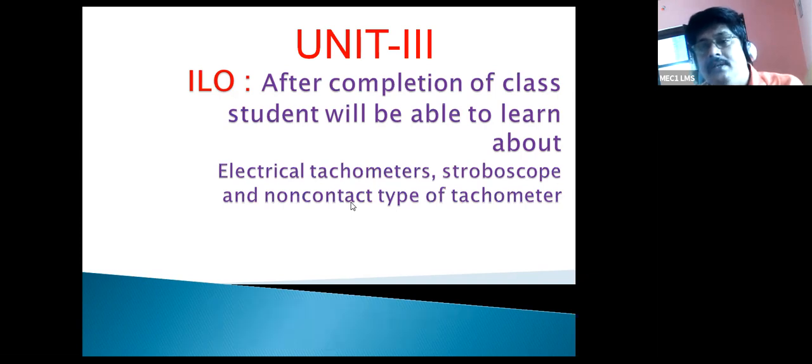The dust particles at the high intensity point scatter the light, which is received by a receiver and sent to the photo detector. The photo detector converts it into an electrical signal, which is the input to the signal processing unit.